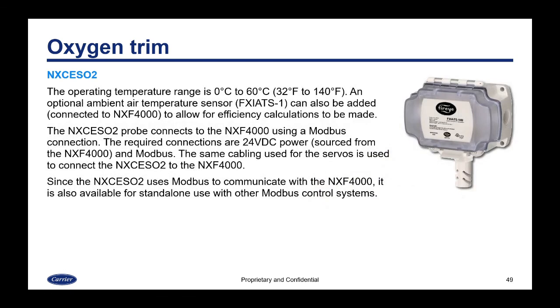With the NXCESO2, the operating temperature range is 0 to 60 or 32 to 140, and that's the ambient temperature around the probe. An optional ambient air temperature sensor can also be added to allow for efficiency calculations to be made, and that would be connected directly to the NXF4000.